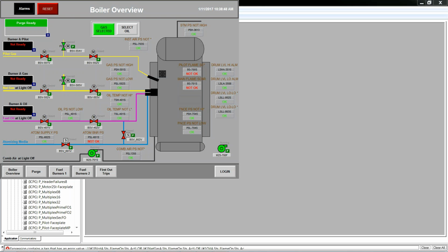It's all standard EtherNet/IP, all standard switches, generally managed switches for the control aspect, but nothing special, all standard off-the-shelf stuff. Now the setup of the historian and the trending takes a little work. That's not out of the box and bam, it's running, because you have to select time slices and data to log and what it looks like and stuff, but completely open application development products.